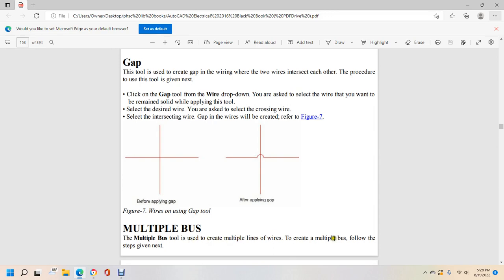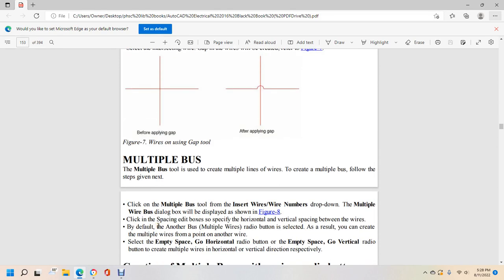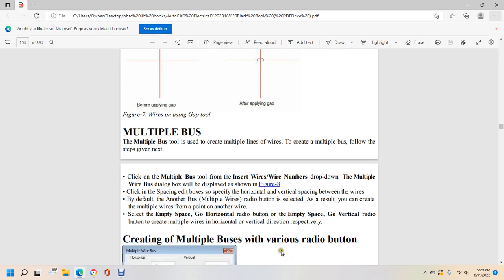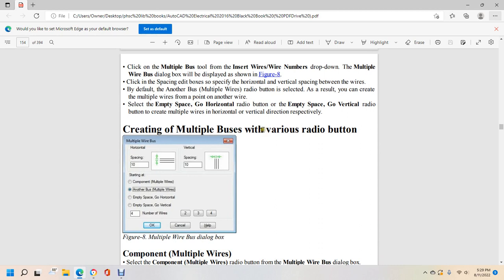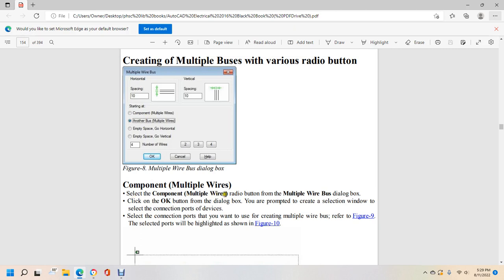Multiple bus. This tool creates multiple lines of wires. Click on the multiple bus tool from the wire and wire numbers drop-down. The multiple wire bus dialog box is displayed as shown in figure 8. Click the spacing edit box to set horizontal or vertical spacing between wires. Select the desired radio button — another multiple wires or empty space go horizontal or go vertical — to create multiple wires in the respective direction. Specify the number of wires as 2, 3, or 4. Click OK, then select the connection points where you want to create the multiple wire bus as shown in figure 9.